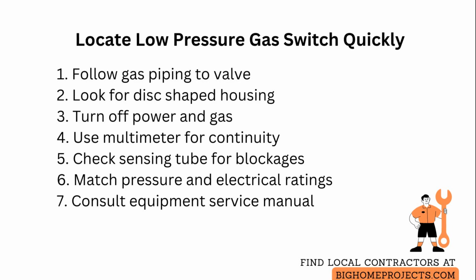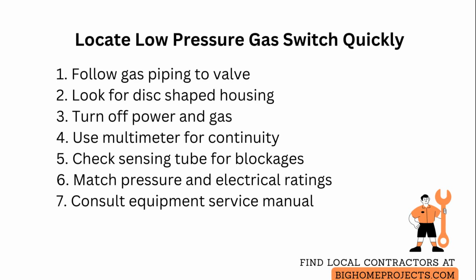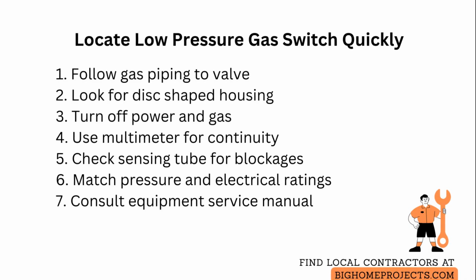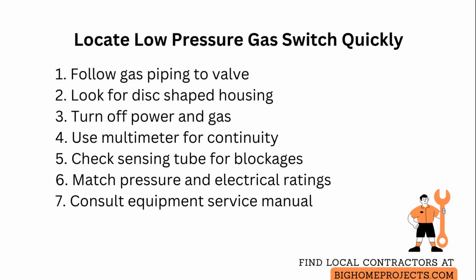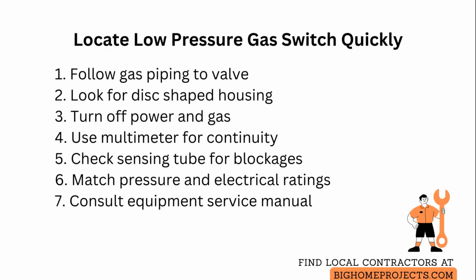To test it safely, first turn off power to the appliance and close the gas supply if you will be disconnecting anything. Then use a continuity tester or multimeter set to ohms across the switch terminals while inducing the operating pressure condition, or carefully press the sensing diaphragm if accessible to observe a change in continuity.